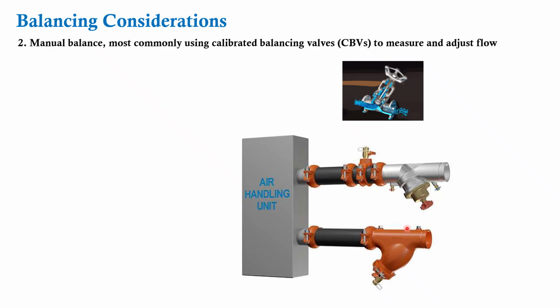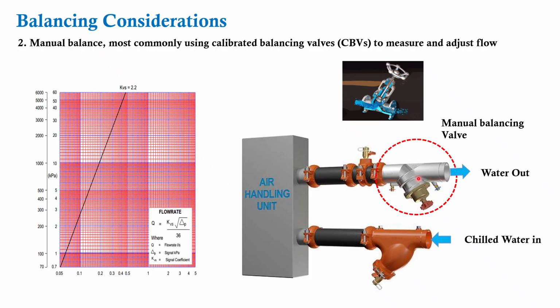If there is an air handling unit, there's a strainer in the supply, and in the return there is a manual balancing valve. It has to be preset for the required flow, which is going to be required for the performance of the air handling unit. So somebody really needs to regulate it manually once, and then the two-way control valve will regulate the flow. So a two-way control valve along with the manual balancing valve can add great value. Here is the inlet and here is the outlet. So this is the performance chart, showing how these valves need to be preset or set for the given flow requirement based on the Kv values.